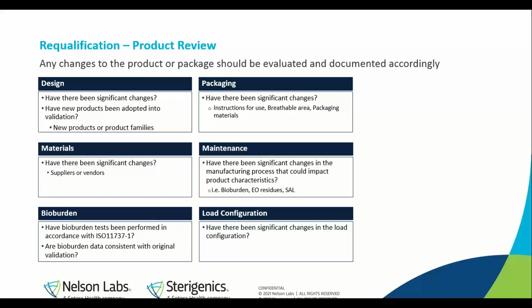Speaking of materials, that brings us into the next phase of review as it applies to the product. Have there been any significant changes to the materials? This would involve any new suppliers or new vendors that are providing any material during the manufacturing process. Once again, part of the product review would be any maintenance. And this would be, has there been any significant changes in the manufacturing process equipment that could impact the product characteristics? Examples of this include a change to the bioburden, the EO residues after the process, and the sterility assurance level of the product. Speaking of bioburden, has the bioburden test been performed in accordance with ISO 11737-1? Is the bioburden data consistent with the original validation after being monitored or trended?